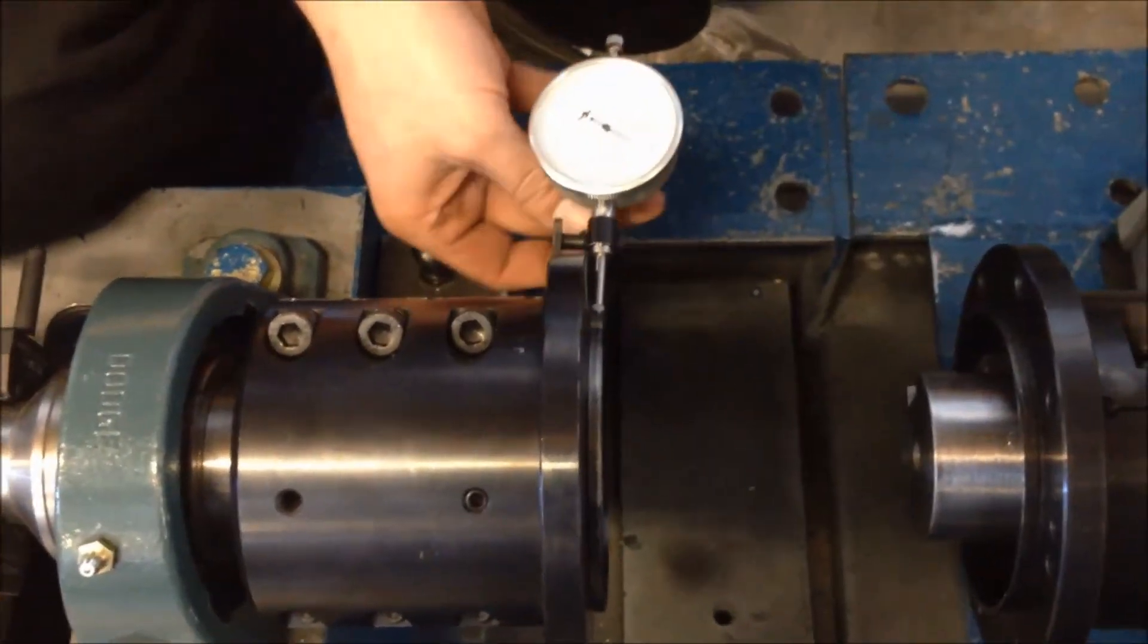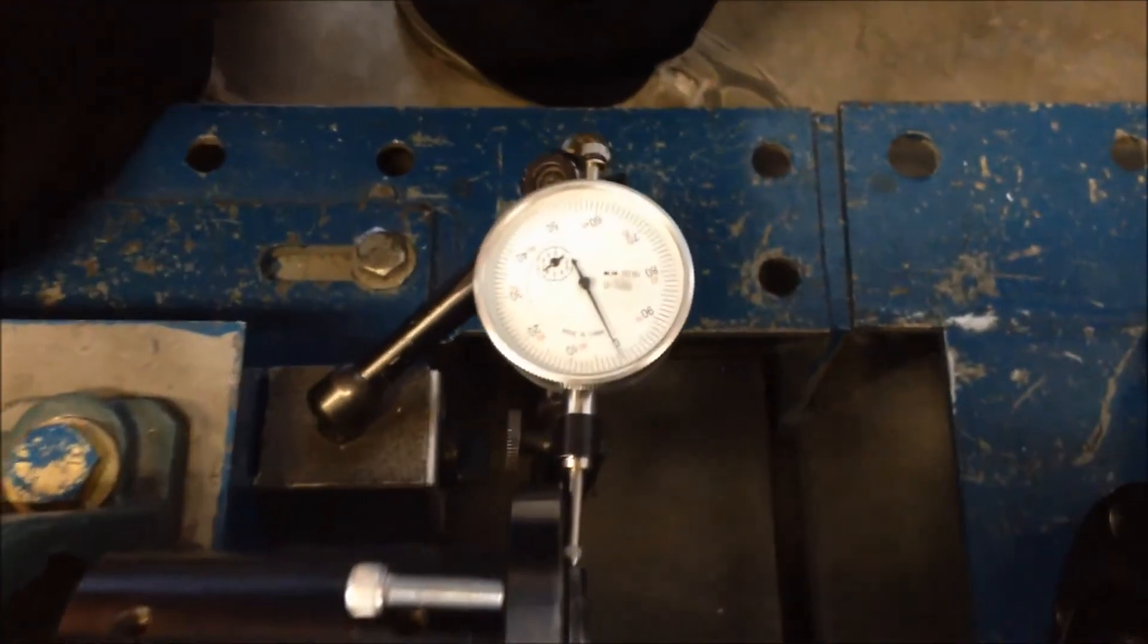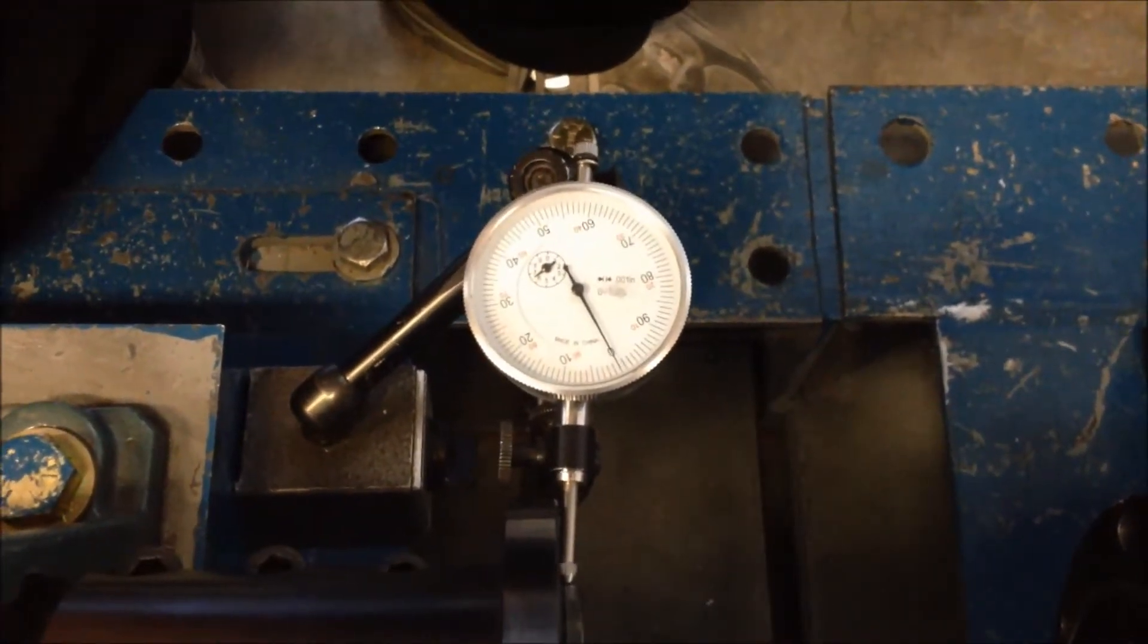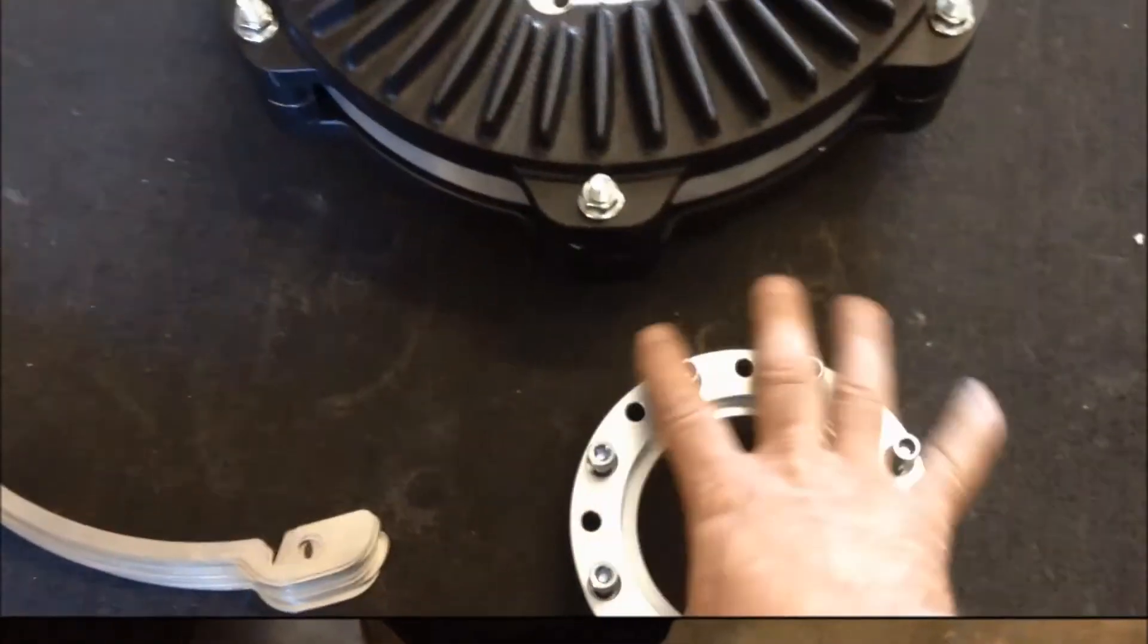Place the dial indicator on the hub pilot and verify that the total indicated run out is less than five thousandths for 1800 RPM applications and three thousandths for 3600 RPM applications.